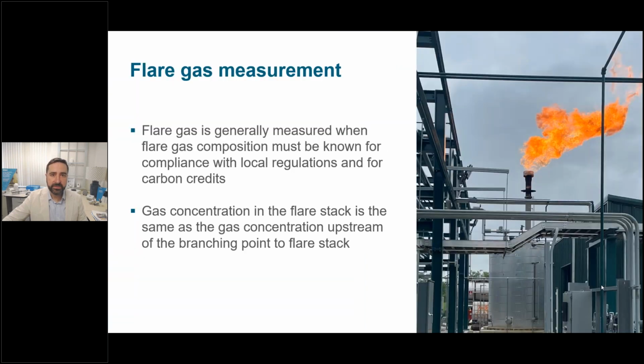And speaking of flaring, accounting for the methane destroyed is an important aspect to assessing the plant's overall efficiency, as well as for compliance. Whether the gas from the digester or landfill is of poor quality, production exceeds upgrading capacity, or the needs of the boiler or CHP, the remainder is diverted to the flare and needs to be accounted for. A complete picture of the methane produced at the site is required, and measuring what is sent to the flare is an important part of that. As flare operation can be intermittent, measurement can be a challenge when the gas is hot and saturated, condensing heavily when sent through the flare line. For this application, we recommend measuring upstream before the diverter, where the concentrations will be the same, but there's less condensation actually happening. Next, please.